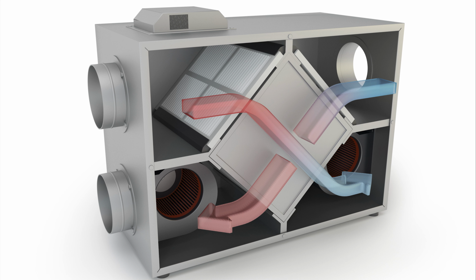Rather than using an air handling unit for the whole building, several simpler heat recovery ventilation systems may be more straightforward to retrofit. These can be small enough to fit in ceiling voids or roof spaces, but serve much the same purpose as the larger air handlers, including having a fixed plate heat exchanger to retain the thermal energy within the building. These kinds of units, although simple, can be expected to recover up to 80% of the heat that would otherwise be vented from the building.